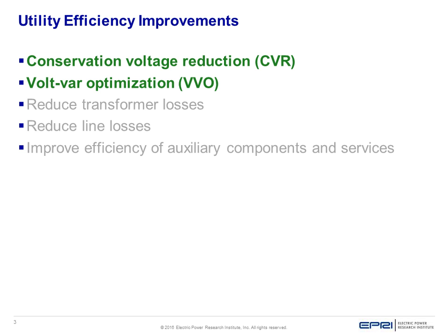For this talk, and for most of this session, we're going to focus mainly on conservation voltage reduction and VAR optimization. Those terms, those programs, are kind of the same thing, and the efficiency gains you get from them dwarf the other options utilities have. Line losses are a component that, at least on the distribution side, might add up to a couple percent of total transferred electricity, so reducing those gives fairly small gains. But the gains in overall societal efficiency are much bigger with CVR and volt-VAR optimization, because those programs can improve efficiency not only on the utility side but also on the end-use side. That's why these two programs are such a focus in the industry today — that's where we can most economically get energy savings.